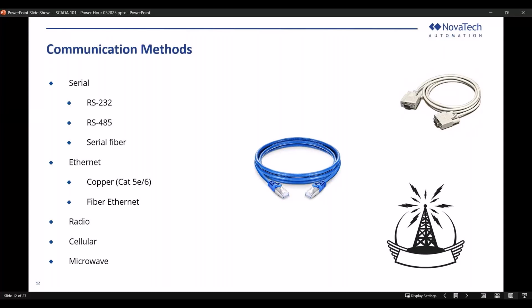Anyone who's ever worked with our Orion MX knows the serial ports on the MX are software selectable between RS-232 and 485. When you go into the web UI and select 485, you'll see the 2-wire and 4-wire mode there. Serial fiber: this one confused me a little bit as a new engineer. I always thought fiber was Ethernet, until I realized there is such a thing as serial fiber. Similar to 232 and 485, you're still dealing with baud rates. It's not network, it's not Ethernet. There's no IP address associated with it. It's point-to-point, similar to RS-232 in that way. Because it's fiber, it transmits light pulses. It is high-speed communication, better for long distance, and unlike 232, it is immune to noise.